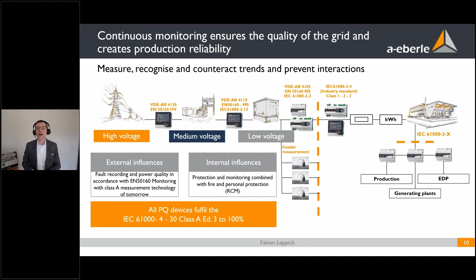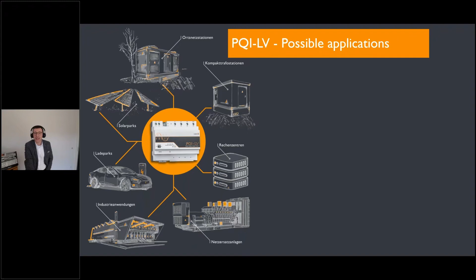You can have a Class S device combined with a Class A device, and both sides measure, for example, a voltage dip differently - the voltage dip of a Class S device is completely different in depth and length compared to Class A. Only a Class A device is able to support and provide reliable measurements.